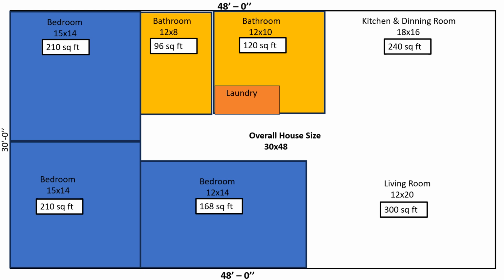Now, if you're looking at the screen, you'll notice this area right here, we don't have any sizing for it at all, because this is where we're going to stick our return. So we could easily mount our return somewhere in this area here, and all the air is going to come through here and naturally help that airflow out. So that's kind of why we're setting this up. And this is strictly to give you an idea of what you need to do, no matter what house you're going into. Or maybe this is an upstairs and you're just doing a 2-ton upstairs. Wherever the unit you're fixing to set is going to be conditioning the air, that's where you need to have this square footage. So we understand these are our numbers for our square feet.